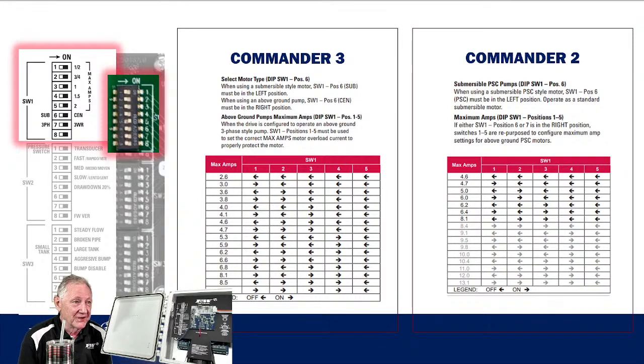Again, when you look at the chart and you set it based on the chart, guess what? You don't have to cross your fingers hoping that you set the drive up properly. You go back up there to, say, 4.1 amps, up in that area. Now you're probably getting down into a 1 horsepower centrifugal motor.